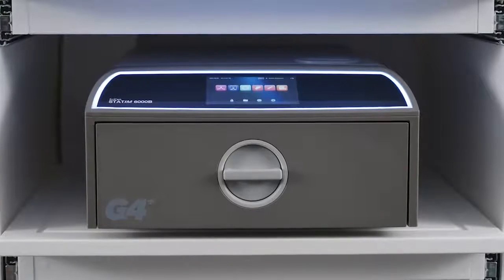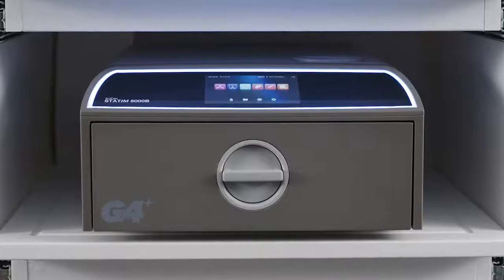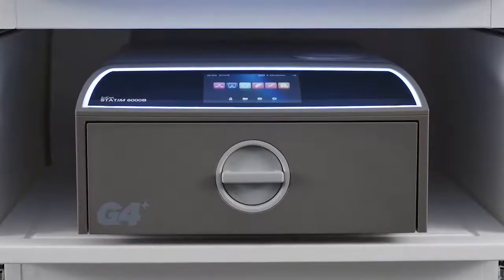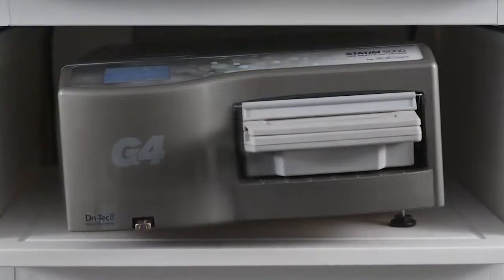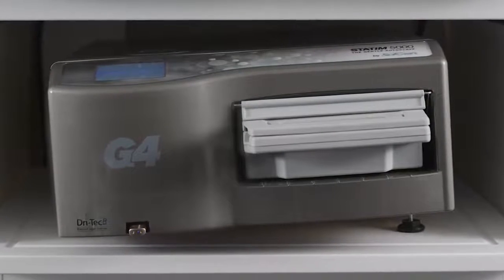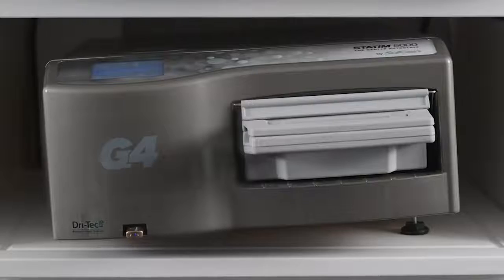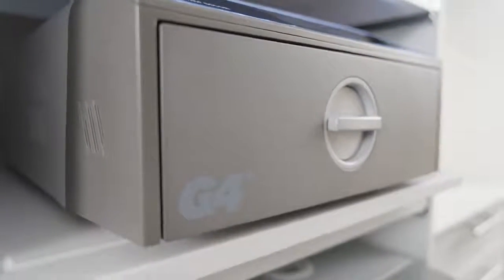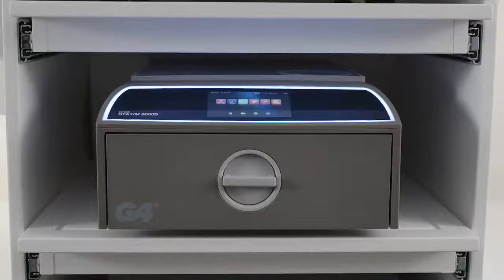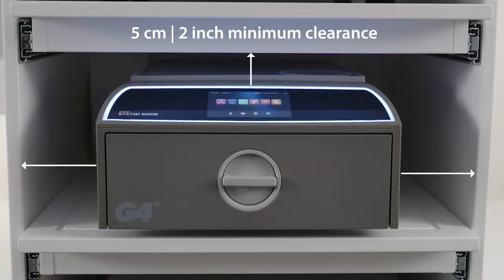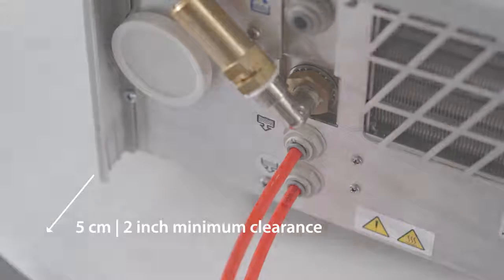The STATIM B is a small footprint sterilizer designed to fit snugly into steri-centers where space can be limited. With the same footprint as the STATIM 5000, the STATIM B fits anywhere a cassette autoclave can. The STATIM B should be installed on a flat, level, water-resistant surface with a minimum of 5 centimeters between the top, sides, and the back of the unit.